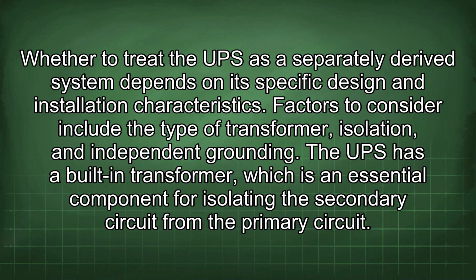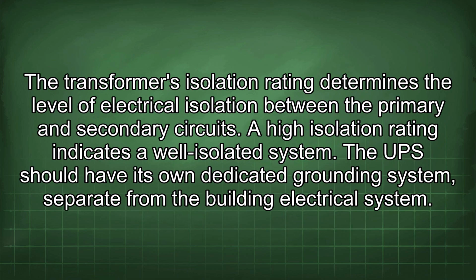Whether to treat the UPS as a separately derived system depends on its specific design and installation characteristics. Factors to consider include the type of transformer, isolation, and independent grounding. The UPS has a built-in transformer, which is an essential component for isolating the secondary circuit from the primary circuit. The transformer's isolation rating determines the level of electrical isolation between the primary and secondary circuits.